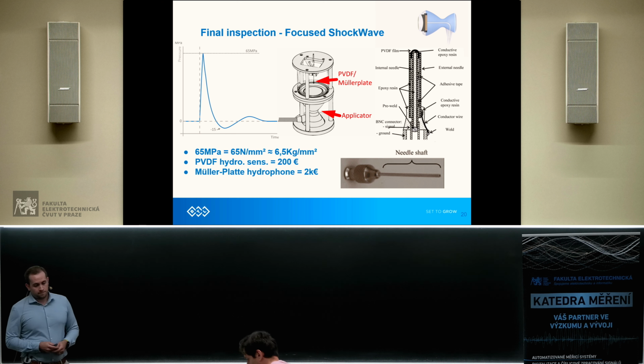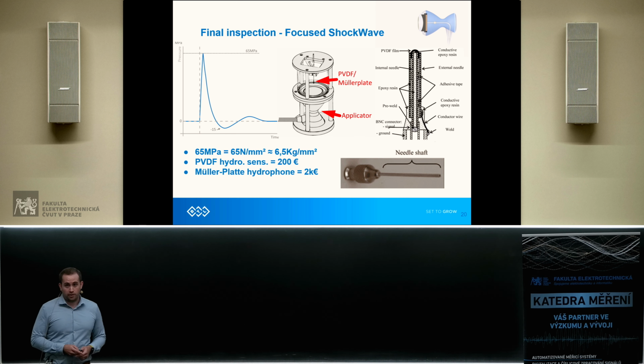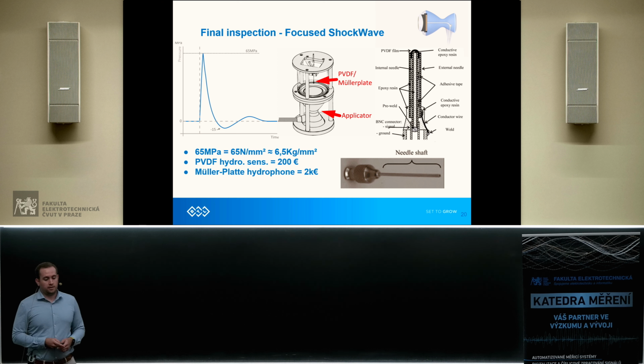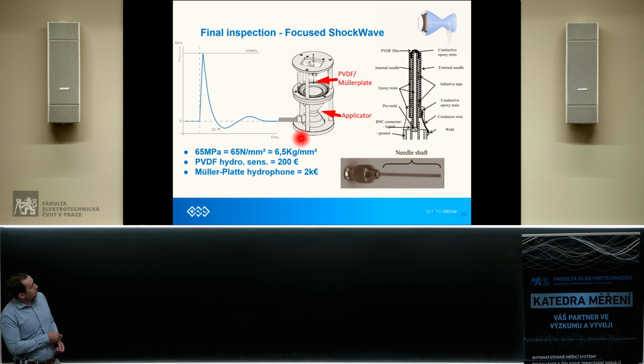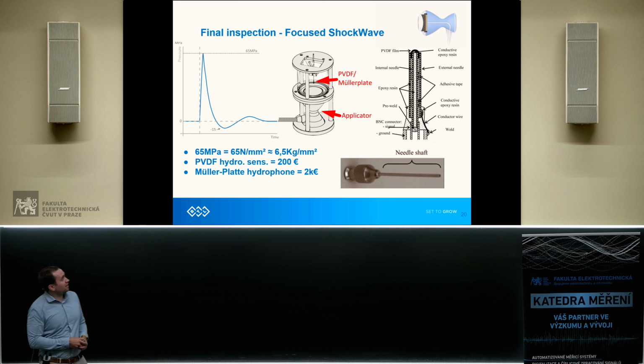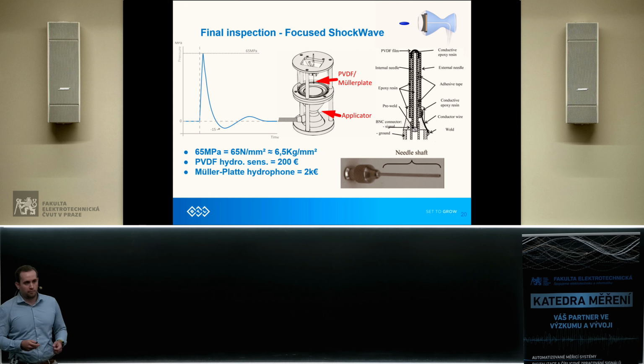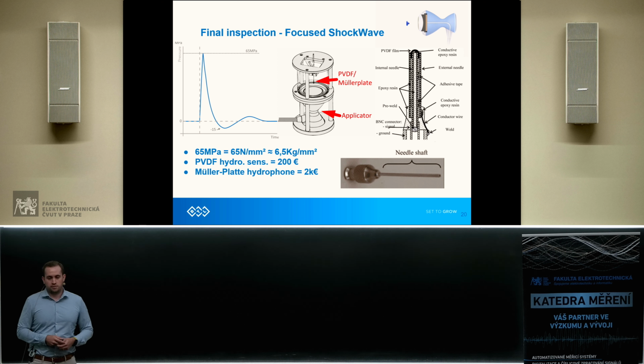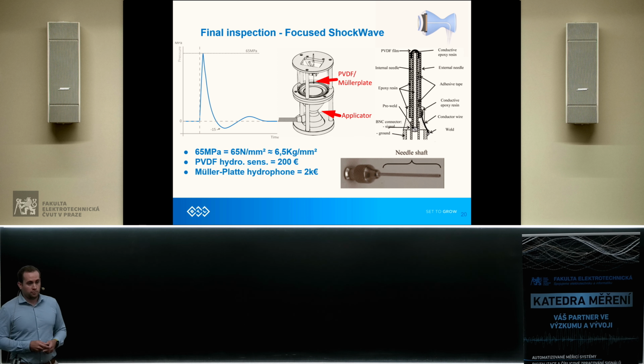And there's my favorite one. That's focused shockwave. I showed you at the beginning that device which does a massive pressure under your skin. Okay, where is it? Over here. See, there is some kind of lens, piezo element, and the focal point is like, I don't know, 5 centimeters below your skin. It does 65 megapascals. So if we calculate a bit, it means 6.5 kilograms per square millimeter. So it's a massive bump into your body, and something we have to measure before this device leaves our production, and we have to be sure that it works fine.